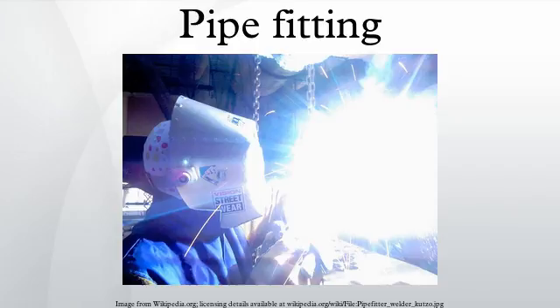without cracking. Soldered connections. Solder fittings are smooth, and easily slip onto the end of a tubing section. The joint is then heated using a torch, and solder is melted into the connection. When the solder cools, it forms a very strong bond which can last for decades. Solder-connected rigid copper is the most popular choice for water supply lines in modern buildings. In situations where many connections must be made at once, solder offers much quicker and much less expensive joinery than compression or flare fittings. The term sweating is sometimes used to describe the process of soldering pipes.